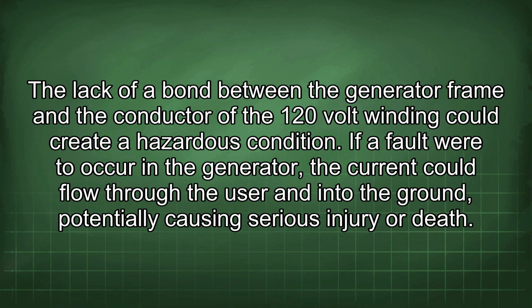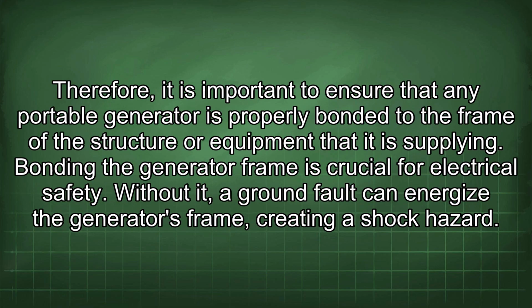If a fault were to occur in the generator, the current could flow through the user and into the ground, potentially causing serious injury or death. Therefore, it is important to ensure that any portable generator is properly bonded to the frame of the structure or equipment that it is supplying. Bonding the generator frame is crucial for electrical safety.